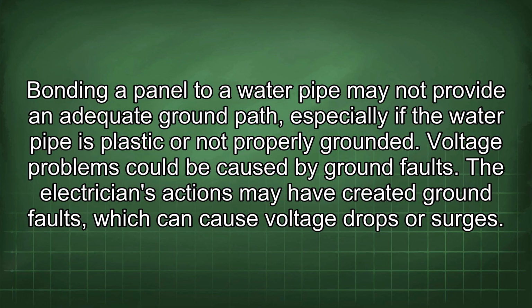Bonding a panel to a water pipe may not provide an adequate ground path, especially if the water pipe is plastic or not properly grounded. Voltage problems could be caused by ground faults. The electrician's actions may have created ground faults, which can cause voltage drops or surges.